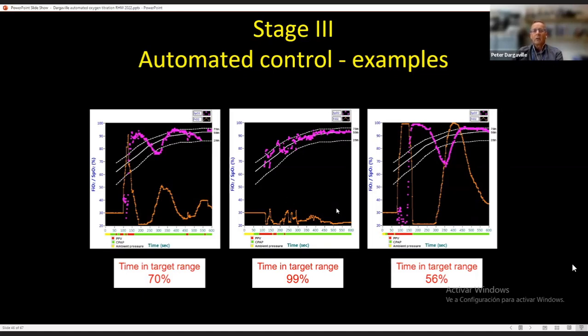The example here in the middle, where the target range time was 99%, shows after the SpO2 is picked up that the starting FiO2 of 30% then alters with the algorithm making adjustments thereafter each second if needed, and keeping the SpO2 well and truly on track in the target range. With yet other instances, particularly in babies who were receiving positive pressure ventilation, like this one was for a good 2.5, nearly 3 minutes, the FiO2 once again can be shown here to bounce around. So we do see a very wide range of responses depending on the circumstances for the individual baby.